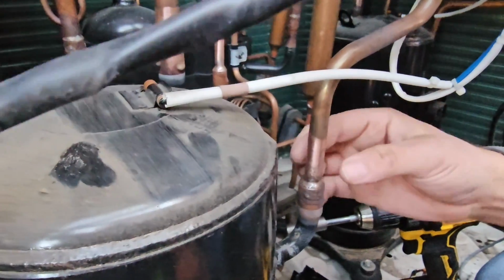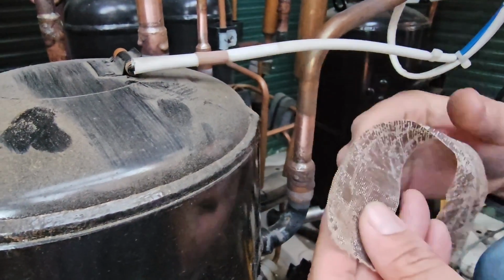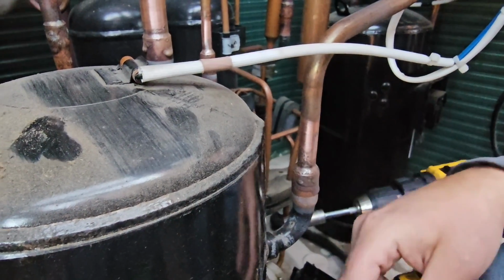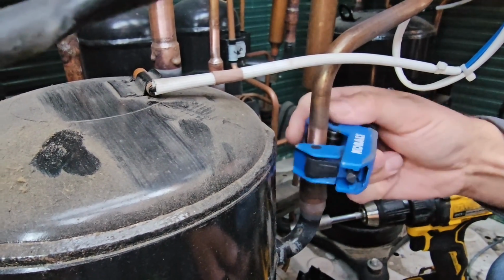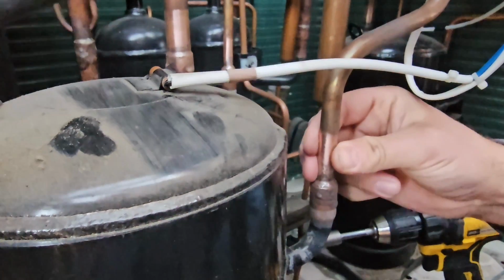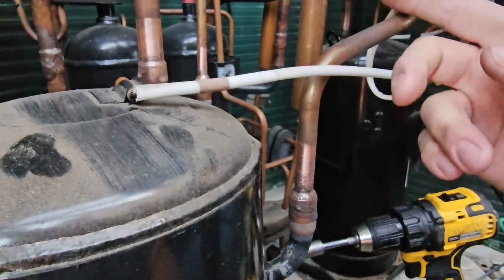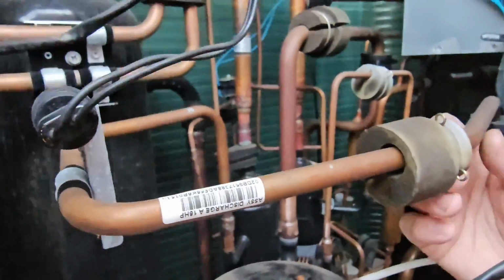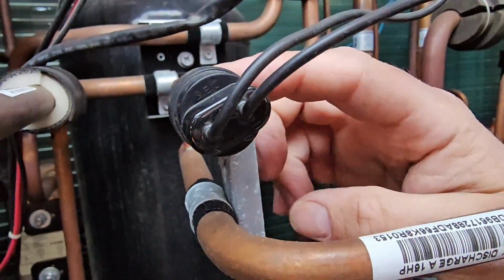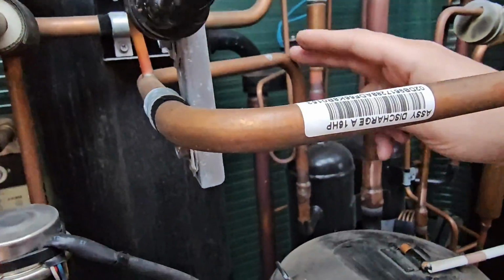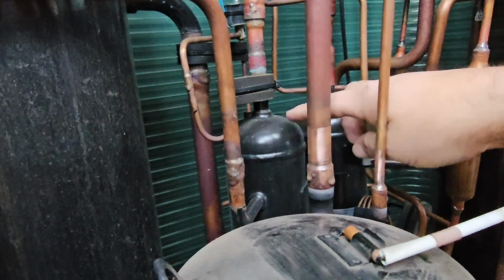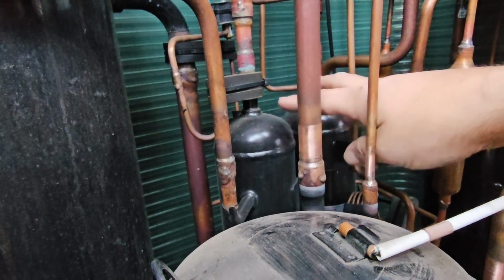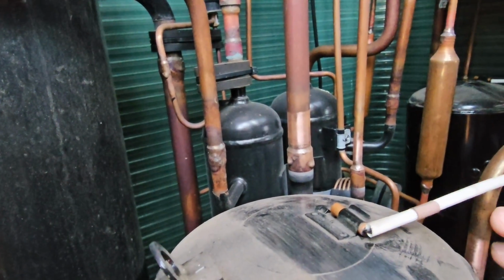So we got 3 pipes, right? And you can see I've used some sandpaper to sand these, because I'm going to use tubing cutters, and I'm going to cut these 3 pipe connections. This is a discharge pipe. How do we know that? If you follow the line up here, you can see there's a high pressure switch right here. And then if you keep following it, it goes into oil separators. So this is our discharge pipe right here.